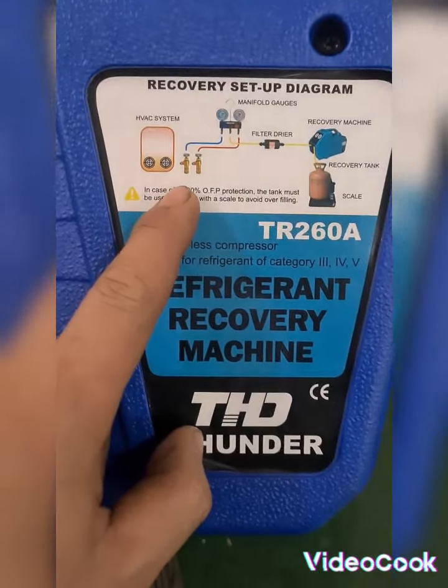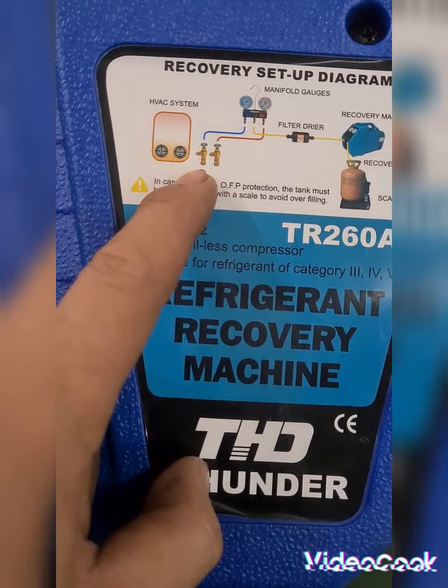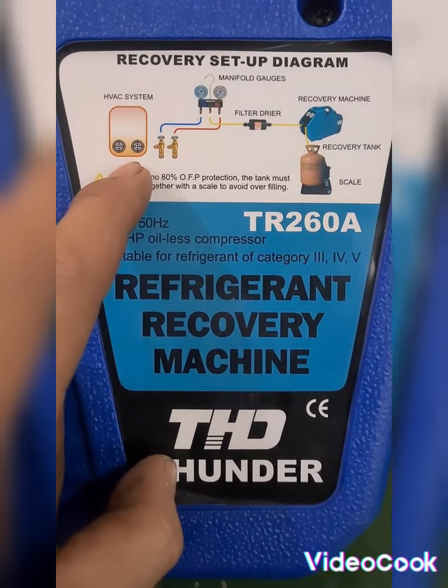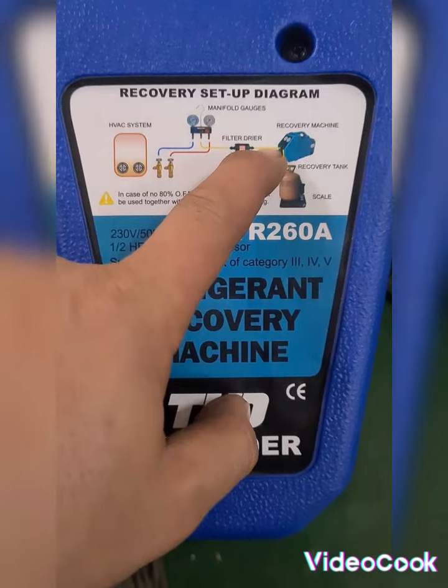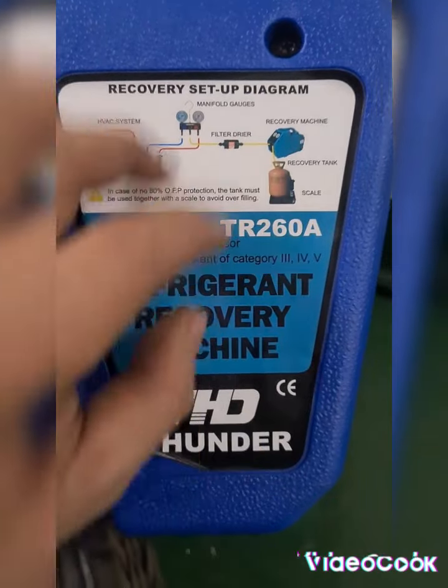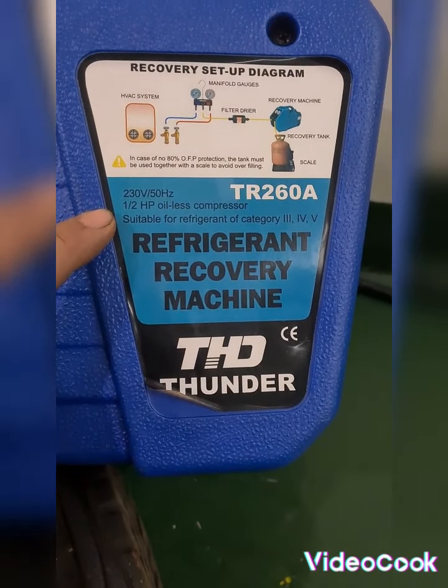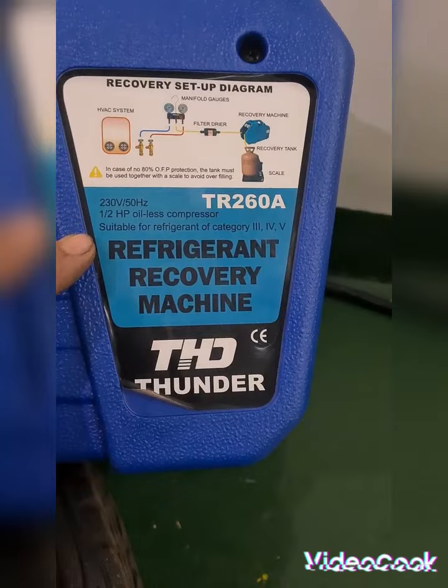I'm going to use the blue color for gas and red color for the liquid from my refrigerant tank. I'm going to put this yellow color to my recovery pump inlet side and the other side on the empty tank. This recovery pump is 230 volts, 50 hertz, 1/2 horsepower, oilless compressor, suitable for refrigerant of category 3, 4, and 5.